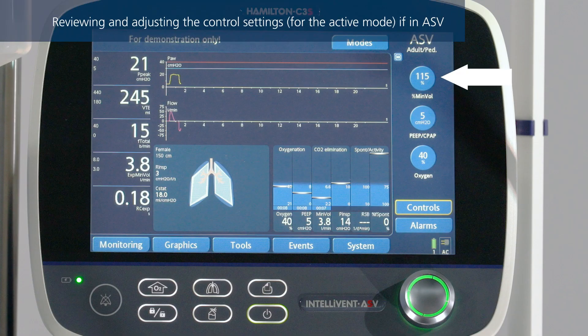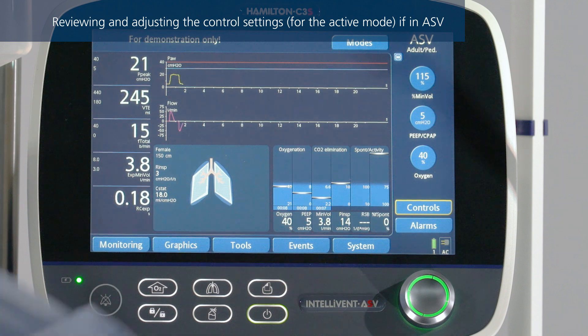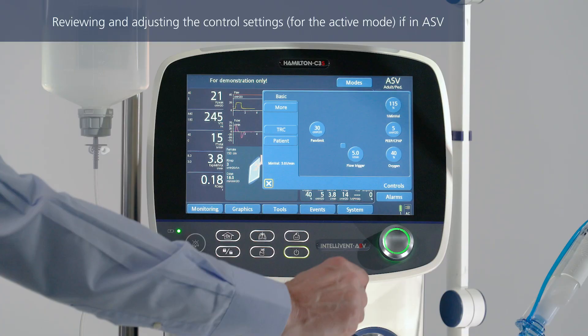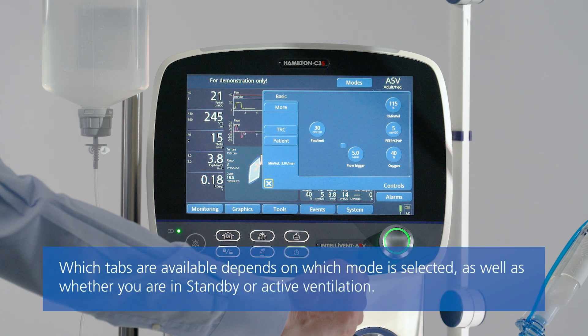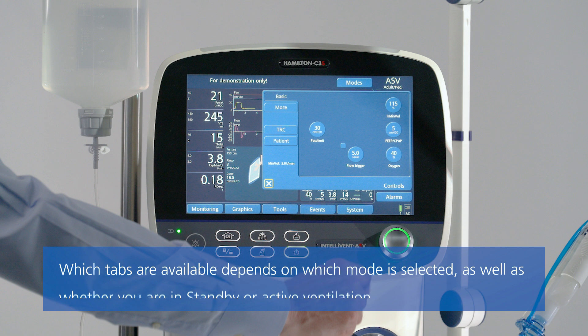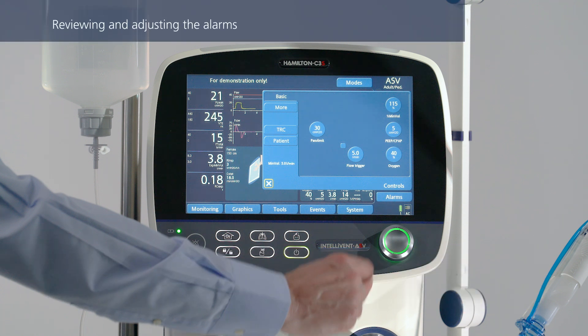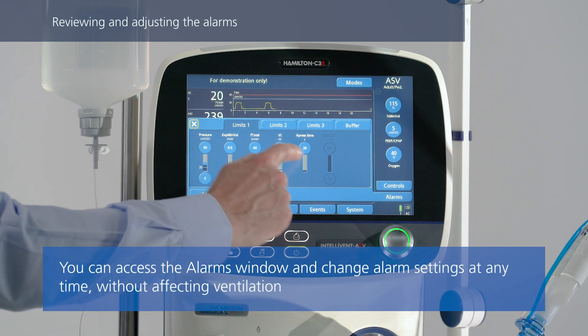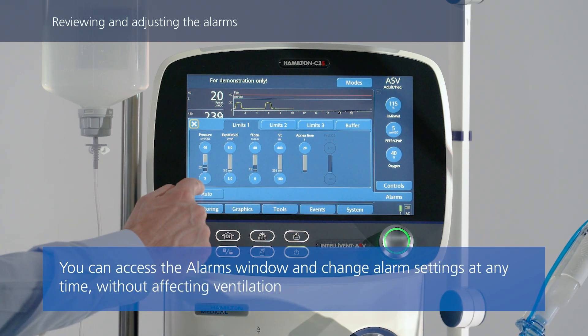To change any control settings, select and adjust the setting or touch Controls to access all the available settings. To review and adjust the alarms, touch the Alarms button. To set alarm limits automatically, touch the Auto button.